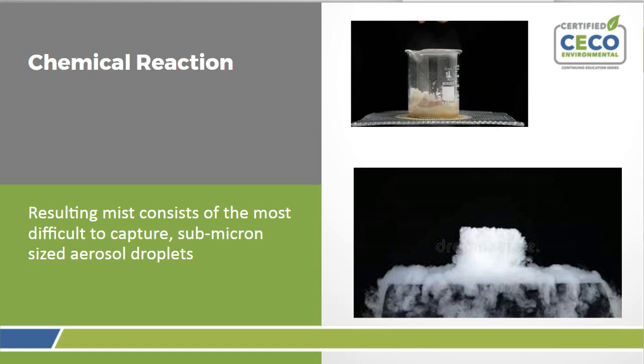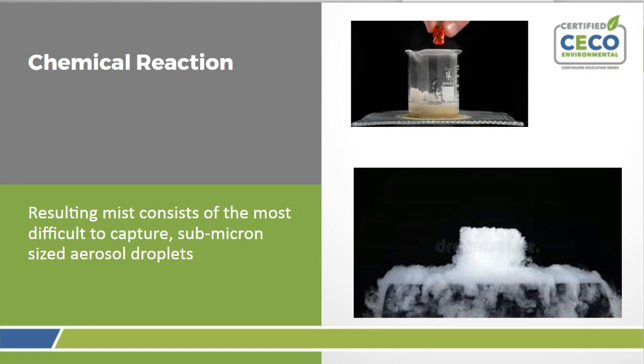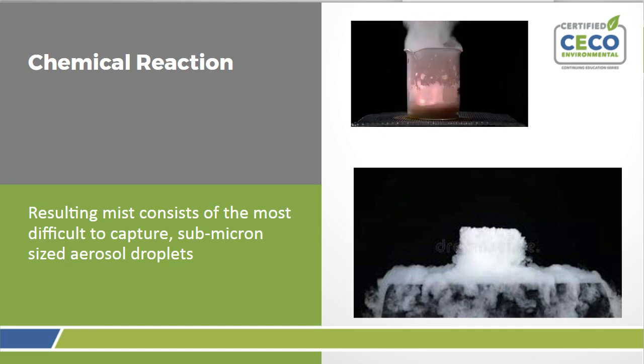Several applications involve chemical reactions, from refineries to incinerators. Even small amounts of sulfur trioxide react with water vapors to form submicron sulfuric acid mist. These droplets create opacity violations and air pollution control hazards. In addition, the presence of mist within the process will impact product purity, and increase maintenance and OpEx. The mean size for chemical reaction processes of a droplet is about 0.3 of a micron or greater.